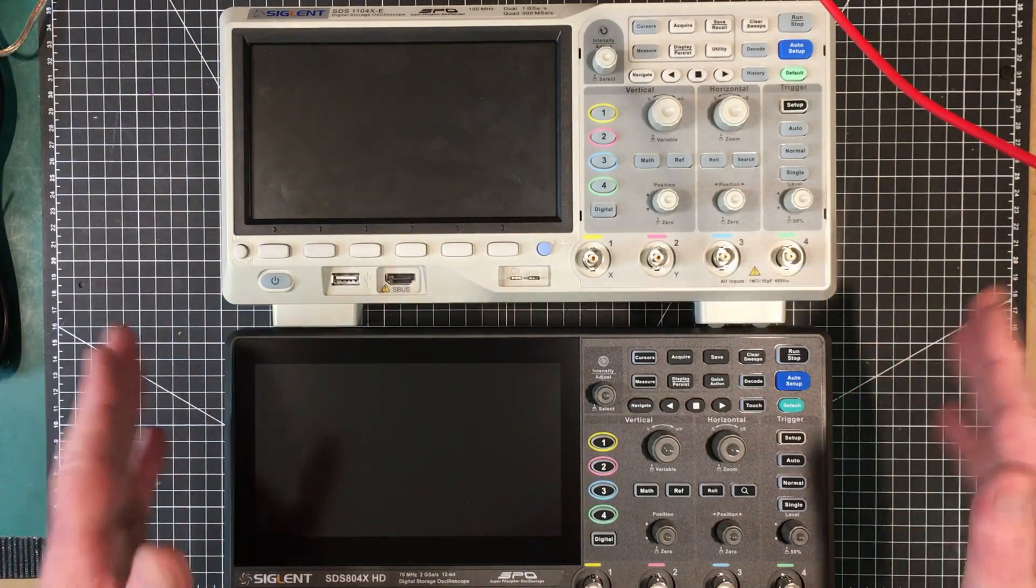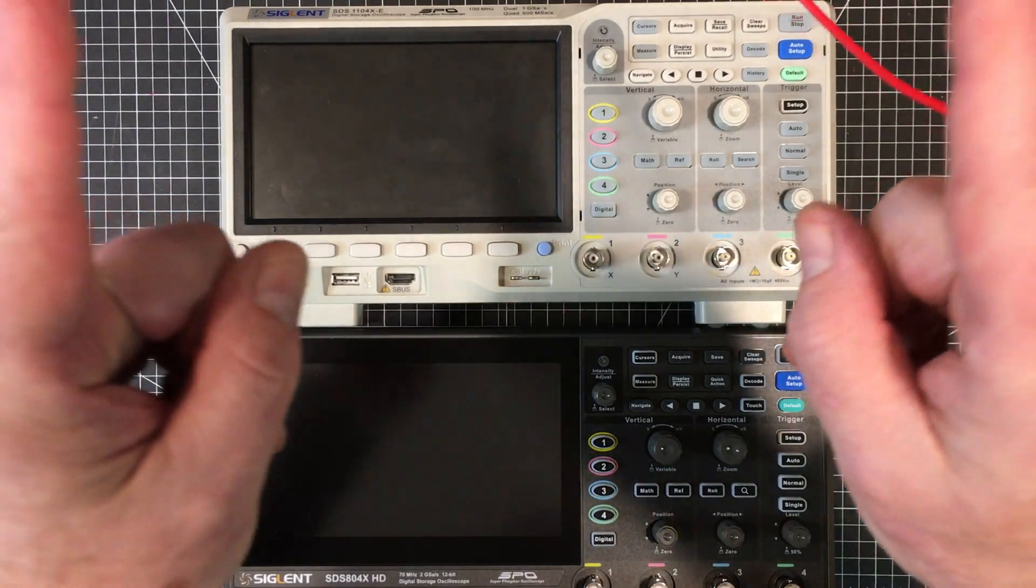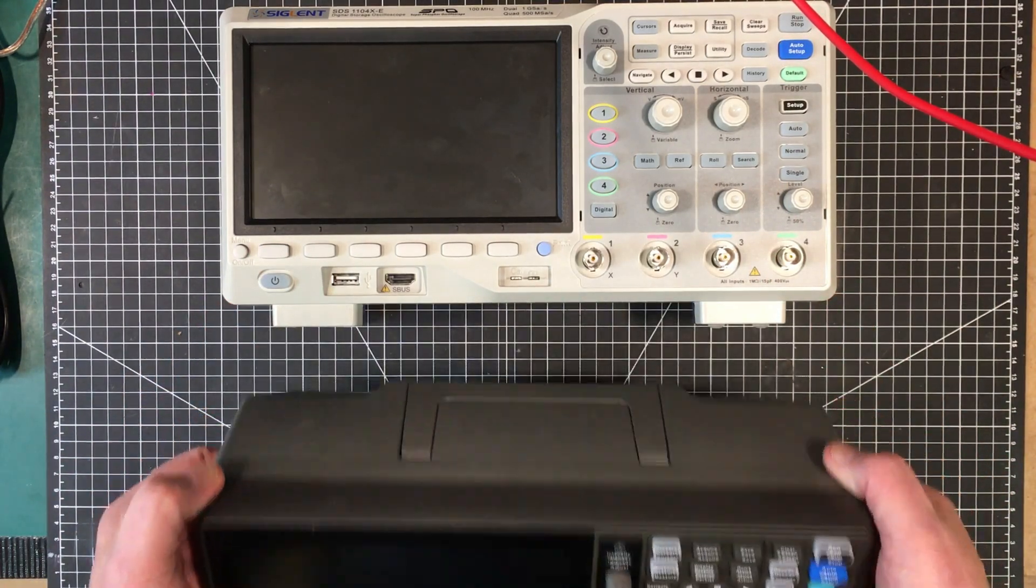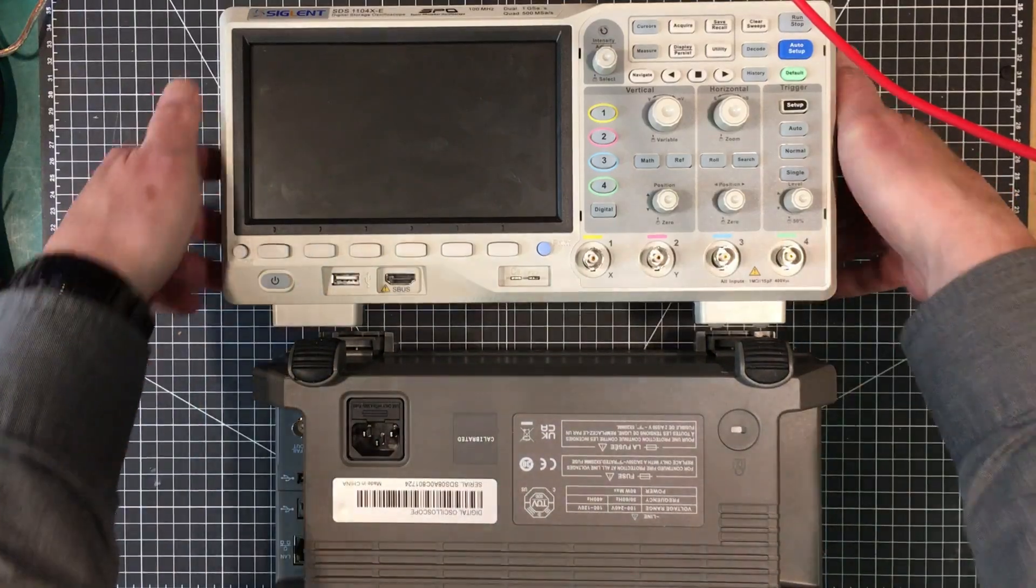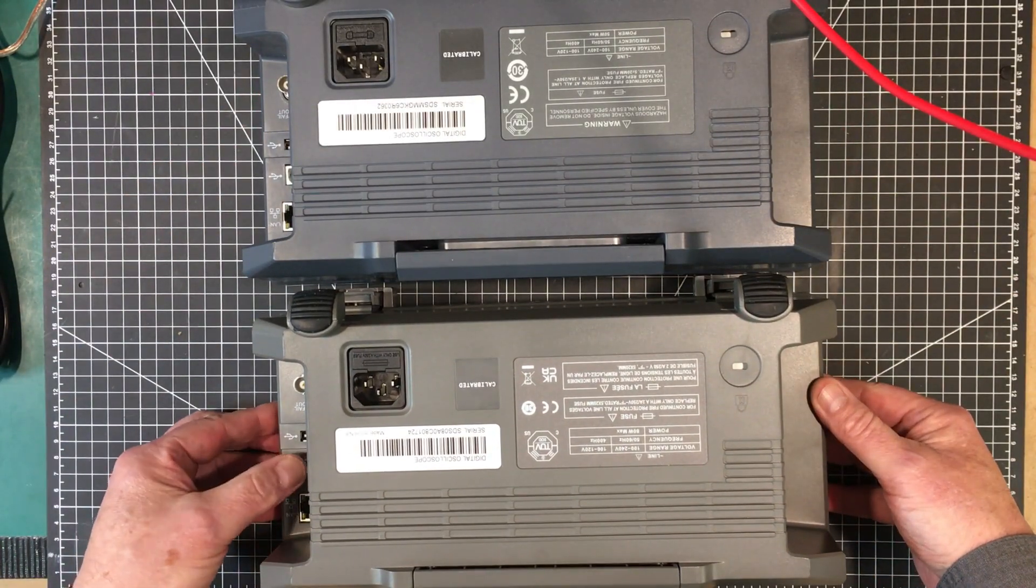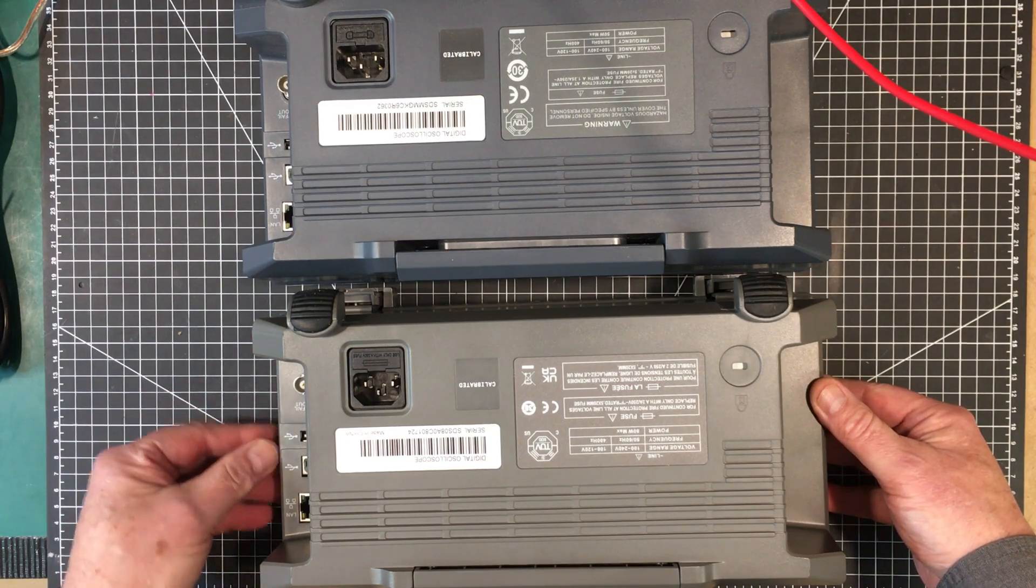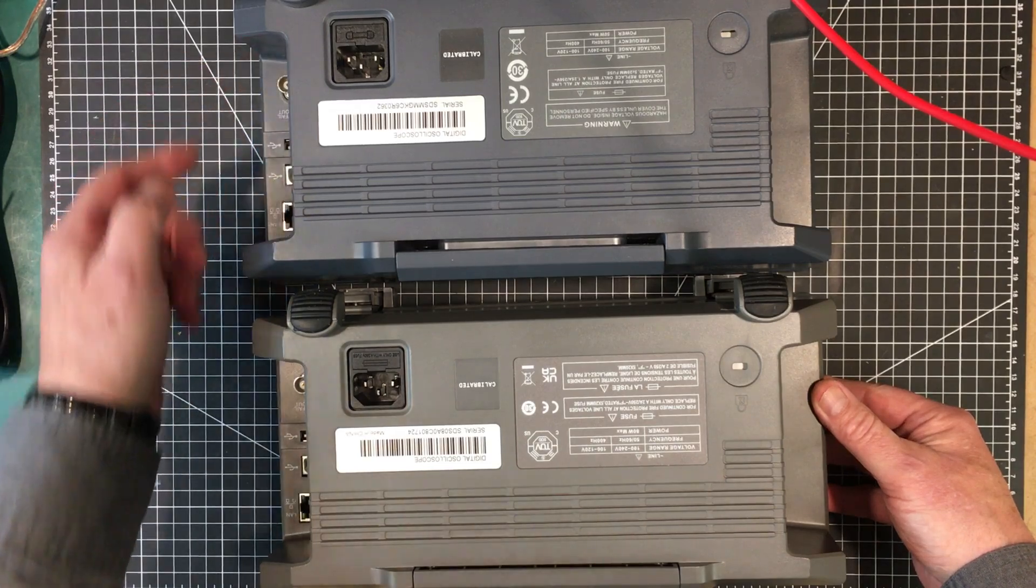This is going to be replacing this. It's exactly the same form factor. So it's going to be able to go back into the same position up here on the bench. It should fit in there absolutely no problem at all. On the back here, anything different? No, exactly the same layout on the back as well. Ethernet port, USB type B, USB type A. Pass, fail, trigger out. And the very same functions on this.